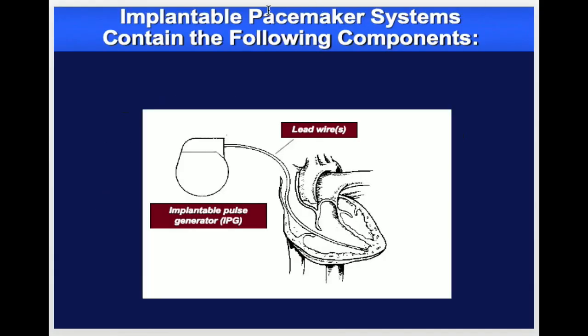A basic cardiac pacing system is made up of an implantable pulse generator that contains a power source, that is the battery within the pulse generator, that generates the electrical impulse. The pulse generator also has a circuit which controls the pacemaker operations. The electrical impulses are transmitted from the pulse generator to the cardiac tissue via leads. The leads are insulated wires that deliver electrical impulses from the pulse generator to the heart. These leads also transmit electrical impulses from the heart to the pulse generator.